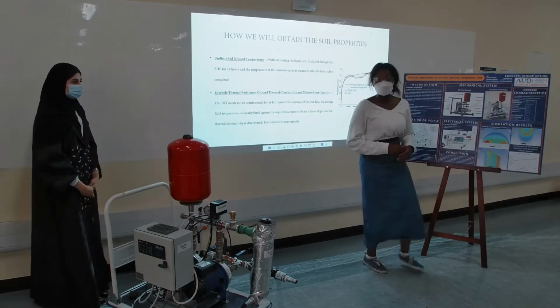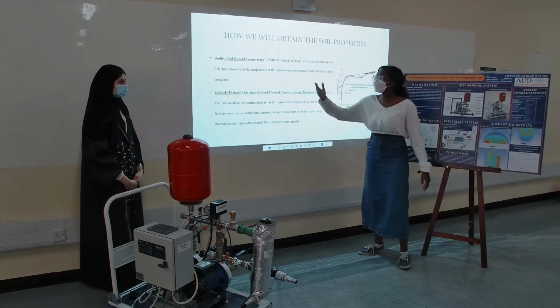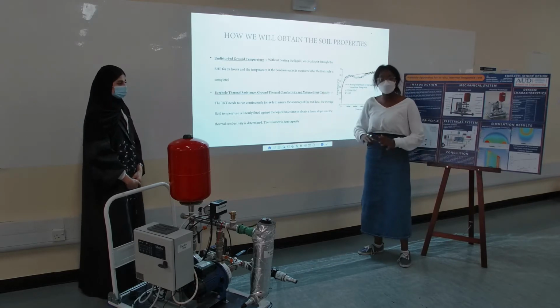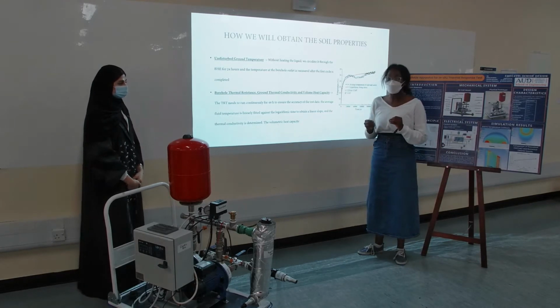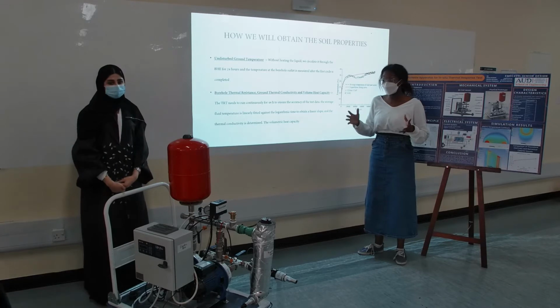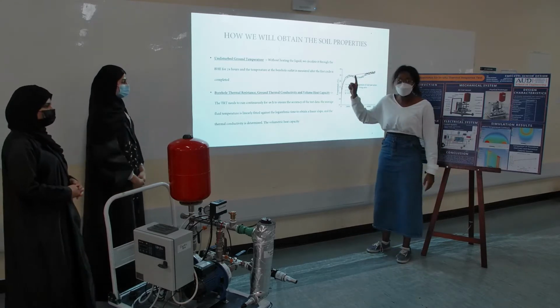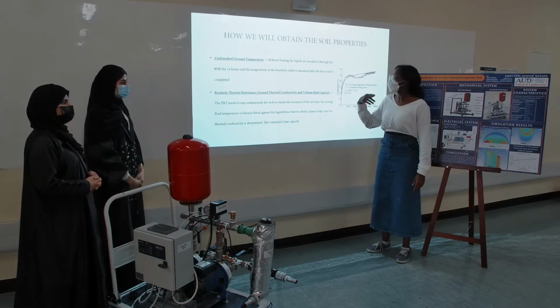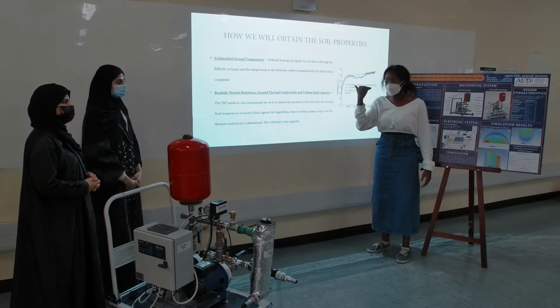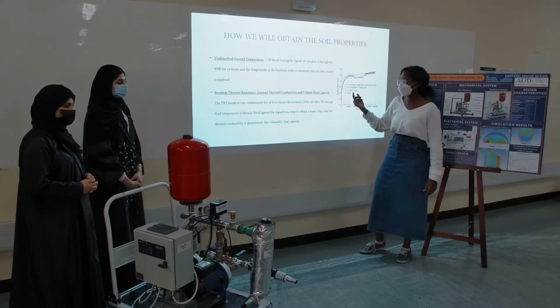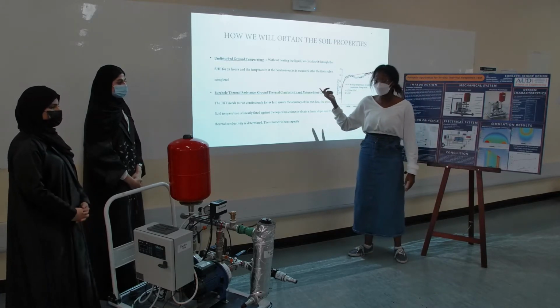So how do we obtain these soil properties? First, for the undisturbed ground temperature, it's simple: for 24 hours we do not attach any heat load, we just run it through the system, and once it completes one cycle, how it behaves at the borehole outlet is measured, giving the underground undisturbed ground temperature.